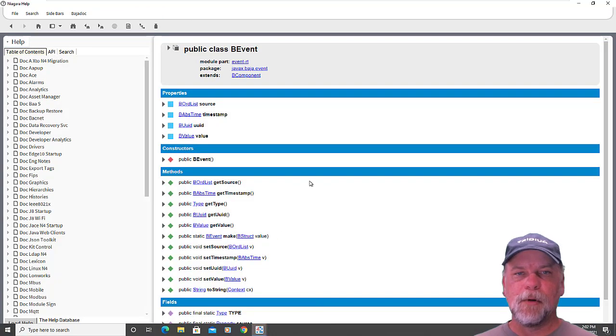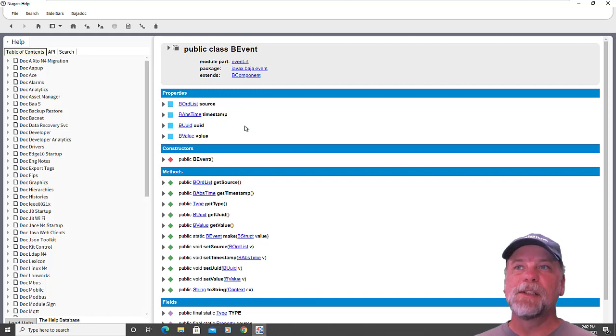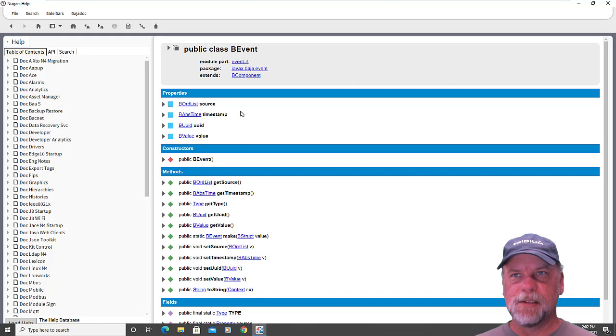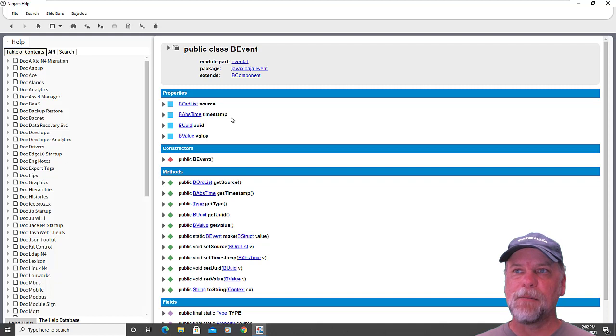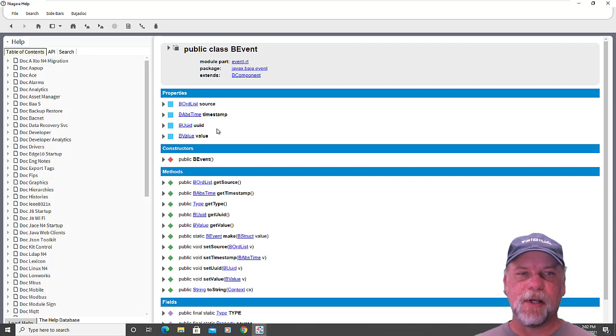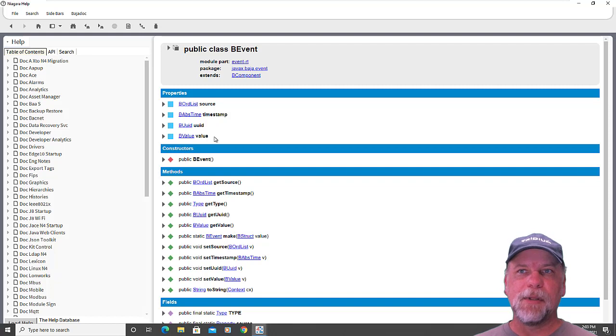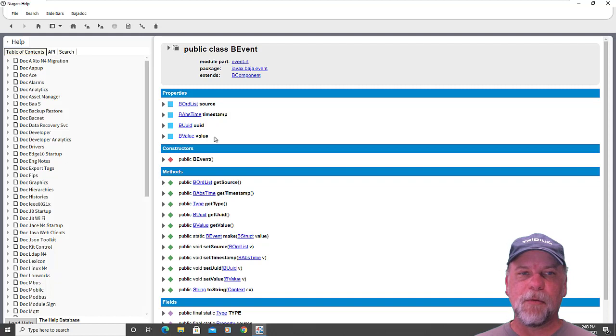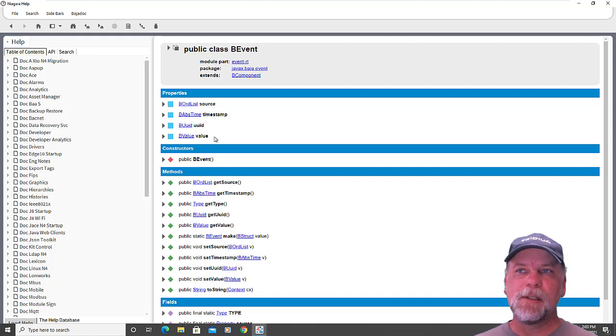Now, if we take a look at the help for a B event, a B event really has four pieces of information to it. There's a source, which is an ORD list that will specify the ORD to the component that the event came from; a timestamp of when the event happened; a UUID, which is just a unique universal identifier for that event in the station. And then there's a value property, which will have some B value — it might be a B status numeric, or a B status boolean if it's coming from a control point, or a B abs time value, or a string, or whatever. There's going to be some kind of a value being passed inside of that value property.